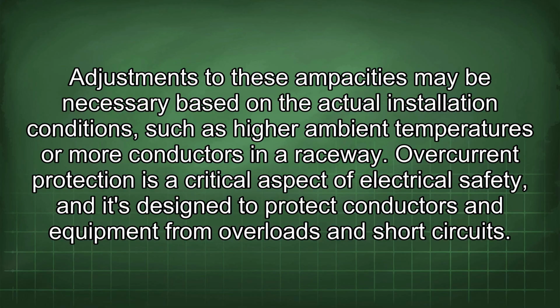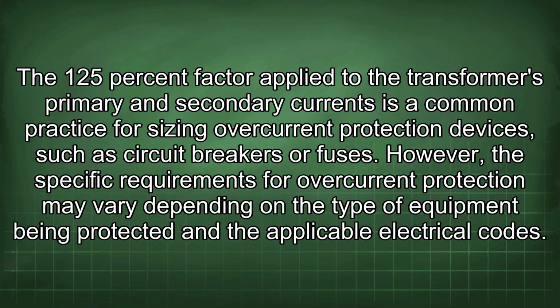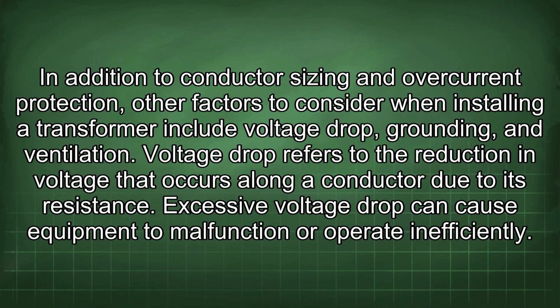Overcurrent protection is a critical aspect of electrical safety, and it's designed to protect conductors and equipment from overloads and short circuits. The 125% factor applied to the transformer's primary and secondary currents is a common practice for sizing overcurrent protection devices, such as circuit breakers or fuses. However, the specific requirements for overcurrent protection may vary depending on the type of equipment being protected and the applicable electrical codes. In addition to conductor sizing and overcurrent protection, other factors to consider when installing a transformer include voltage drop, grounding, and ventilation. Voltage drop refers to the reduction in voltage that occurs along a conductor due to its resistance. Excessive voltage drop can cause equipment to malfunction or operate inefficiently.